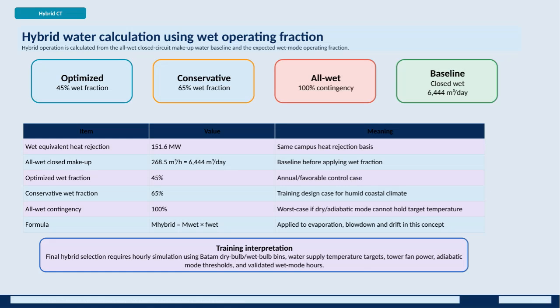Here we dive into the concept of hybrid cooling towers, or hybrid CT, with a focus on calculating water use based on the wet operating fraction. Essentially, the hybrid operation water calculation starts with the baseline water usage of an all-wet closed-circuit system and adjusts that according to the expected fraction of time the system operates in wet mode. We have three key wet mode scenarios here. The optimized case assumes a 45% wet fraction, representing a more efficient, favorable operational scenario.